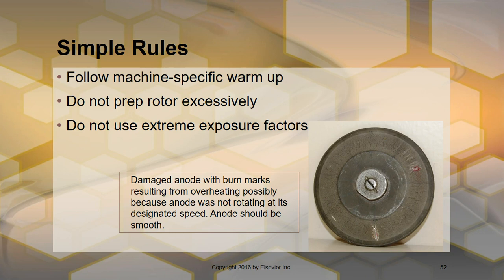There are times when the unit says, if we haven't taken an x-ray in 3 hours, we need to warm it up before we take another x-ray, because you could risk cracking the tube. Now, newer units may have automatic warm-up, but if not, make sure that you warm it up just like you should. This is for our Minnesota people: if you have 5 below degree temperatures, you don't crank your car and jump right out into the road with it. You should let it warm up just a little bit. We don't have that problem as much here in Florida.